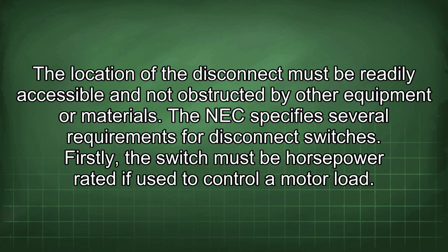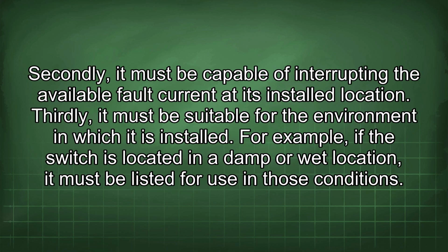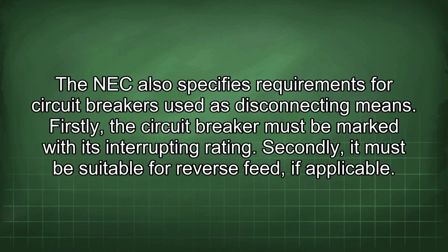The NEC specifies several requirements for disconnect switches. Firstly, the switch must be horsepower rated if used to control a motor load. Secondly, it must be capable of interrupting the available fault current at its installed location. Thirdly, it must be suitable for the environment in which it is installed. For example, if the switch is located in a damp or wet location, it must be listed for use in those conditions. The NEC also specifies requirements for circuit breakers used as disconnecting means.